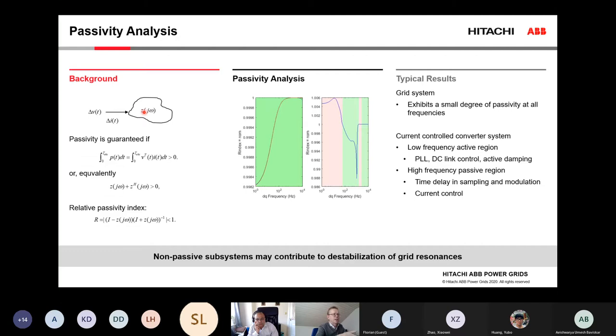And if that power is positive, it means that the device is absorbing power. So if you have a resonance excited in the grid, your device, in the regions where it's passive, will dissipate the energy in those disturbances or oscillations and damp them out. On the other hand, if you are non-passive, so if the power is negative, it means that you might be amplifying such variations at resonance frequencies and contribute to an instability. And there is a function to calculate this R index. It's in MATLAB. So if you have the impedance representation as a transfer function matrix, you can very easily calculate the passivity. And it's a very useful tool for the control design.